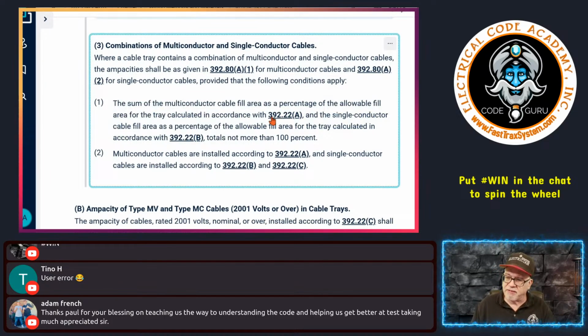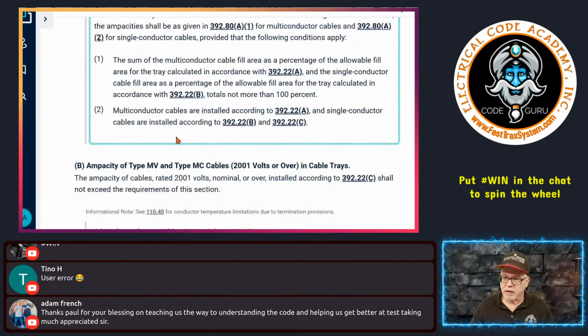And that means you have to follow 392.22(A) for the cables. You have to follow 392.22(B) for the single insulated conductors. Whatever their fill is, and whatever their fill is for those combined, they cannot be more than 100% of whatever that tray's allowable volume is, okay? And it says multi-conductor cables are installed in accordance with 392.22(A). We saw that. And single conductors shall be installed in accordance with 392.22(B) and whatnot, okay? So that type of thing.